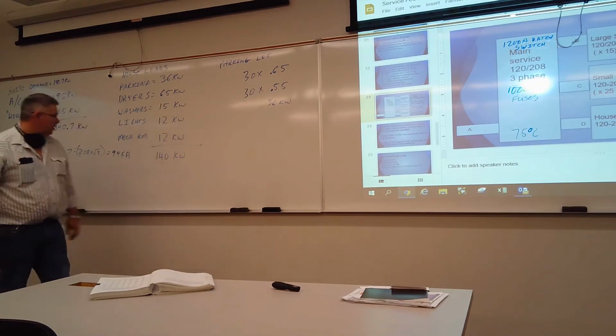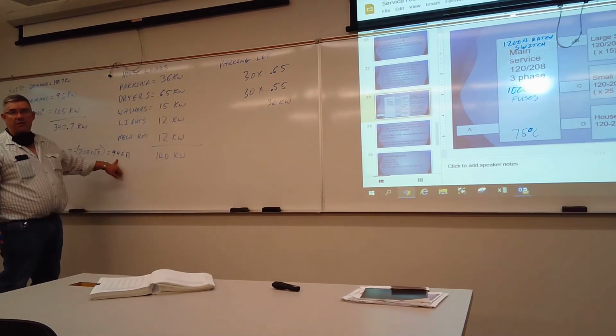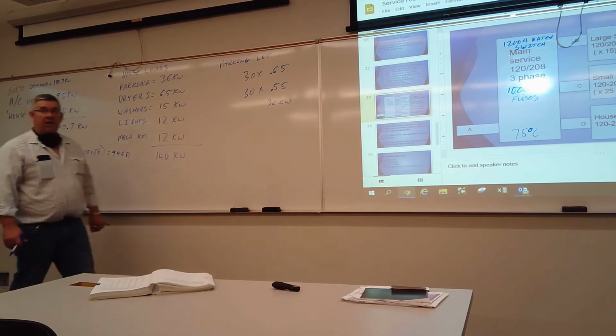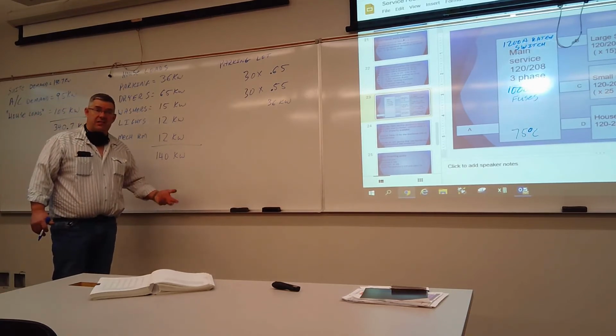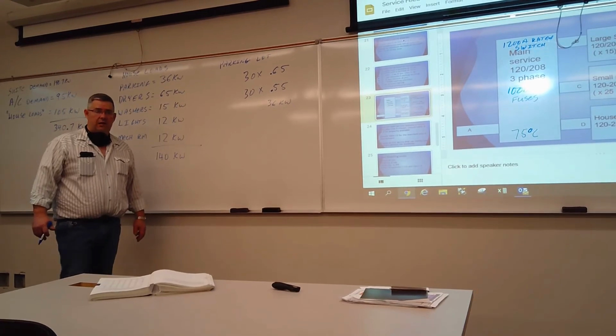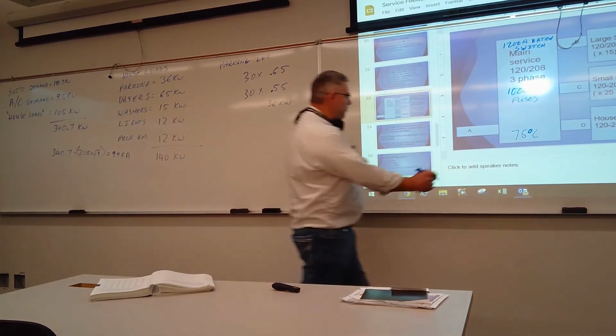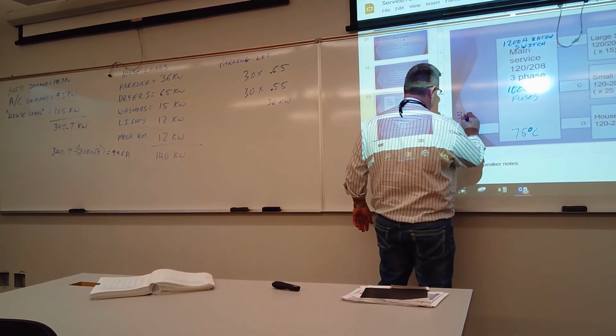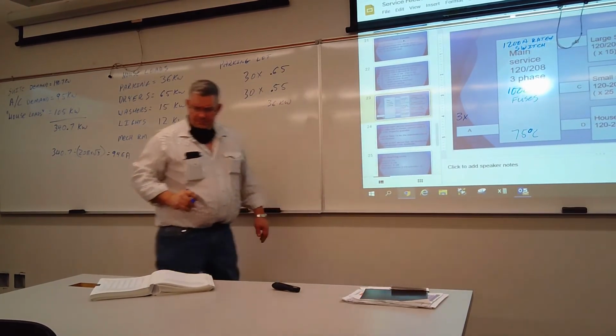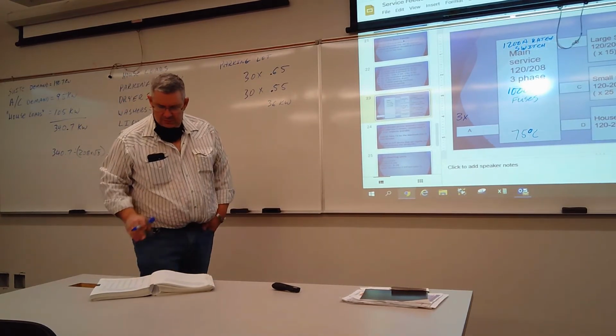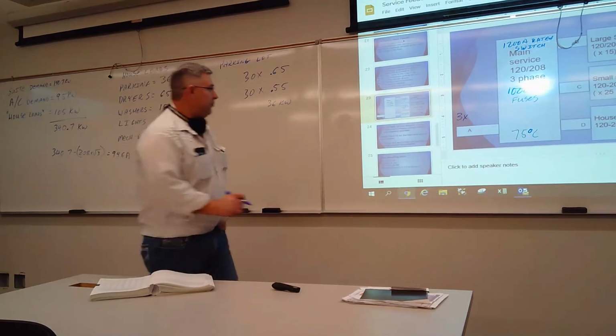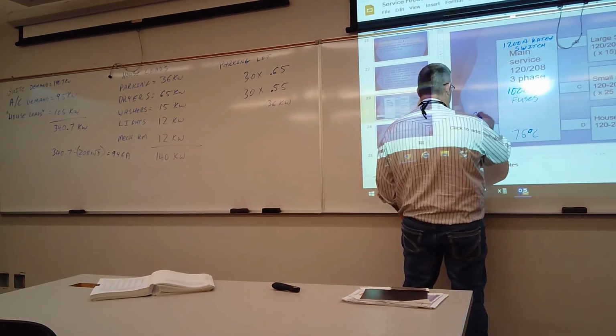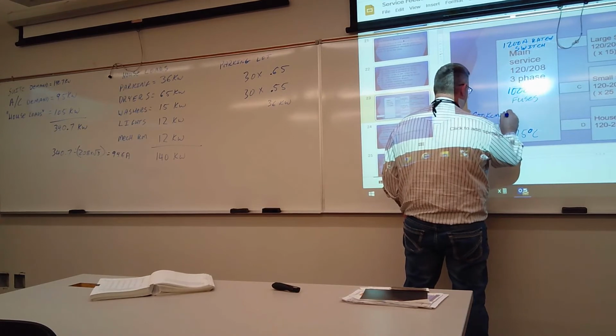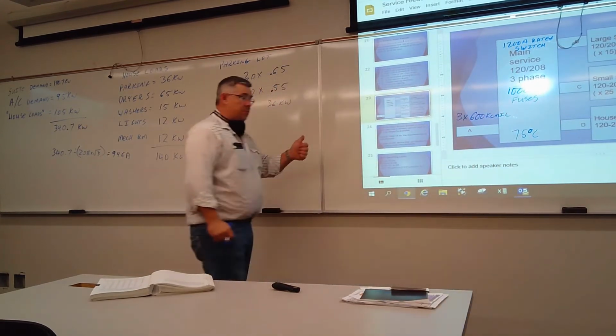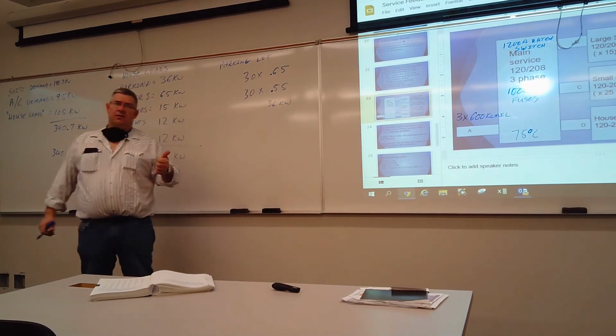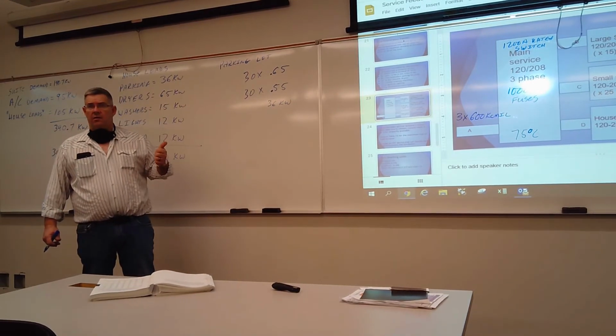That was pretty big. Why don't we just split it in three? We take our 946 and split it in three, and that gives us 316 amps apiece, right? So we could do 3 runs of 600s. Good for 340 amps, sure. So that means we're gonna have, how many conductors in total?